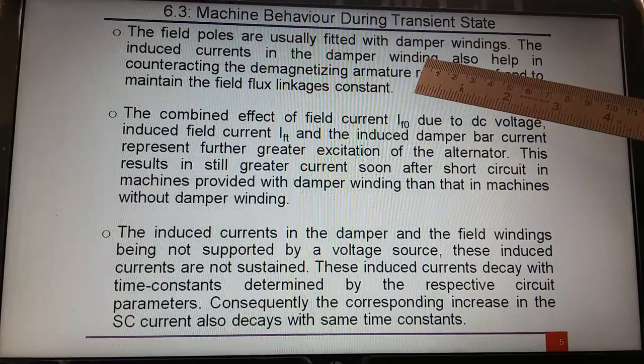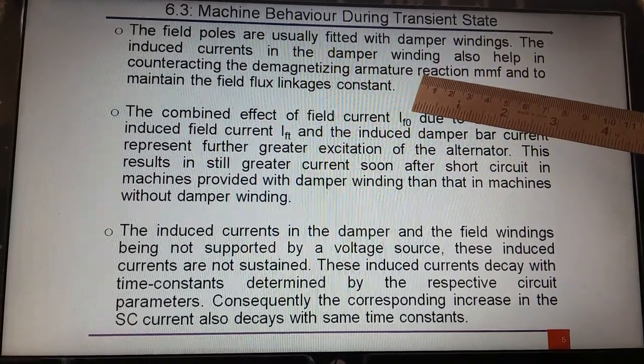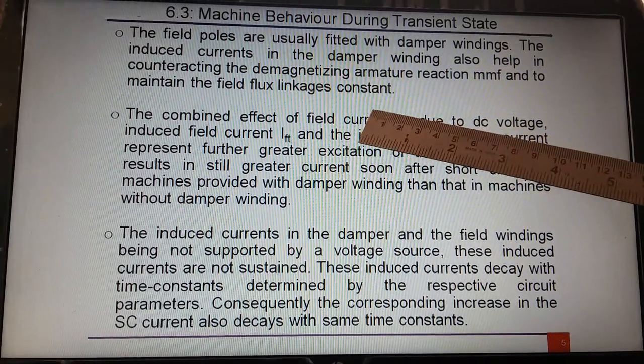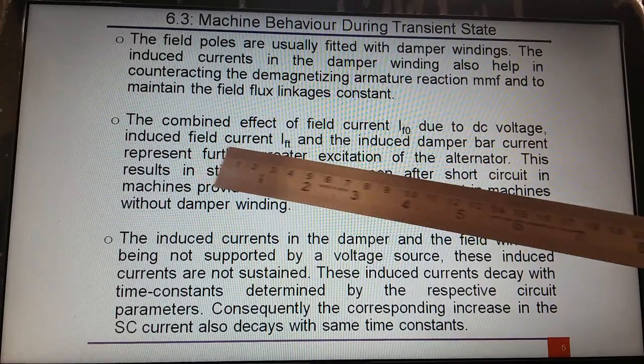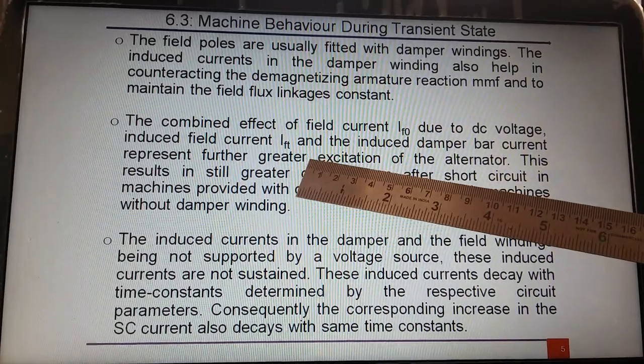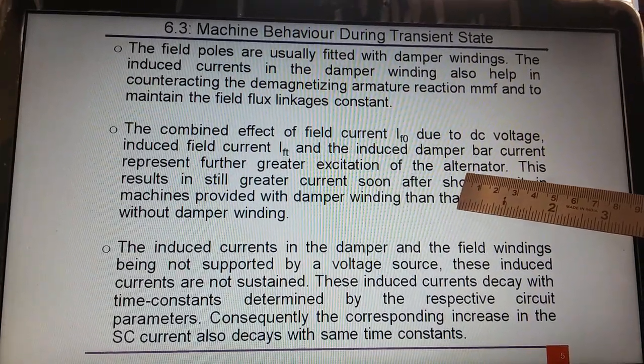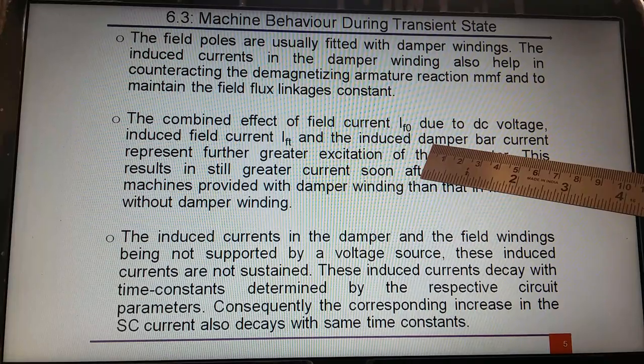Along with the induced field current, the field winding is already supplied with DC voltage, so that current is already present. The field current due to DC voltage is there, and additionally there is the momentarily induced field current and the induced damper bar current. These all result in greater excitation — IF is increasing, excitation increases, and short circuit current also increases. However, all this momentary induction — the induced field current and induced damper winding current — are not supported by any voltage source, so these effects will die out after a certain period of time.